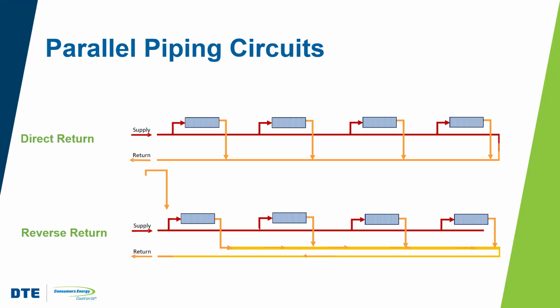So here, the branch that's close to the pump on the supply side is farthest from the pump on the return side, and vice versa. So this helps to correct that flow and balance. But even with that, there are some other differences with this system. For example, the piping for the reverse return system: on the supply side, the pipe gets smaller the farther away from the pump you get. You want to make sure that you have accounted for that. On the return side, the pipe gets bigger as you come back. I want to make sure that for both of those, we're modulating that pipe size to maintain a head loss of about 4 feet per 100 feet of pipe.